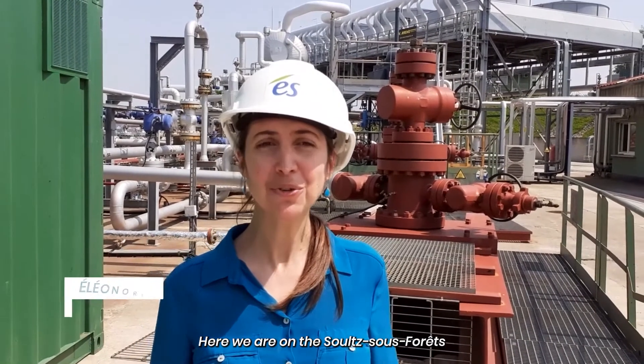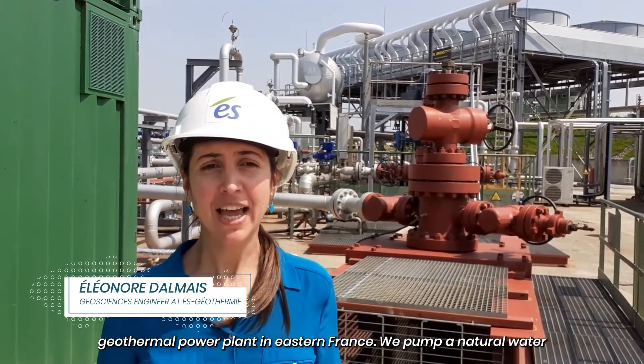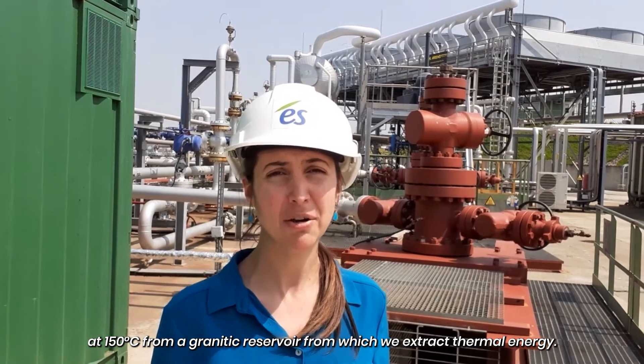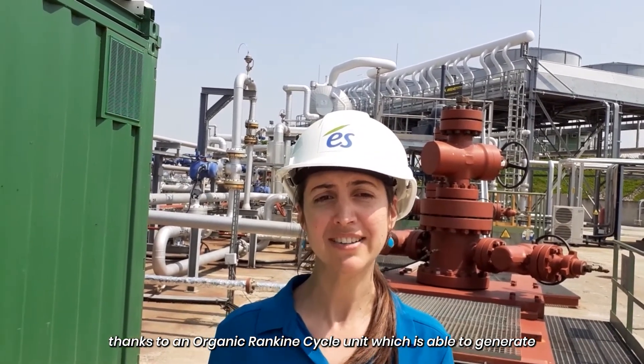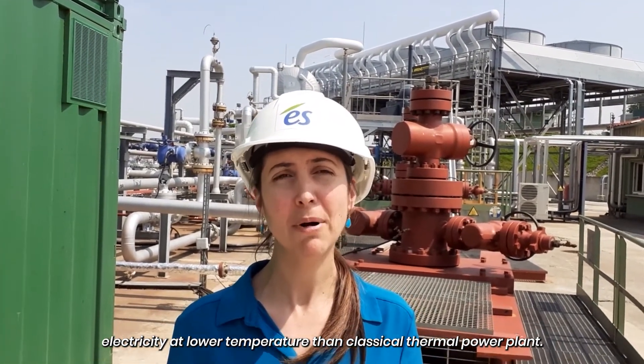Here we are at the Soultz-sous-Forêts geothermal plant in Eastern France. We pump natural water at 150 degrees from a granitic reservoir, from which we extract thermal energy. The water is then re-injected at 70 degrees into the same reservoir. The thermal energy is converted into electricity thanks to a low-enthalpy organic Rankine cycle unit, which is better suited to generate electricity at lower temperatures than classical thermal power plants.